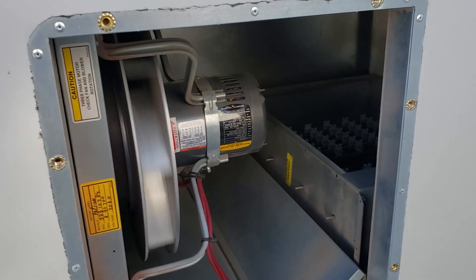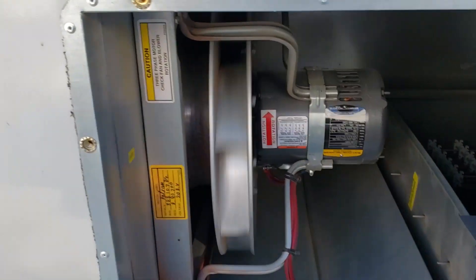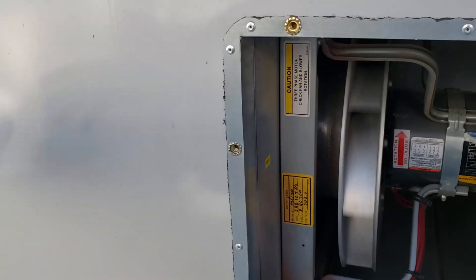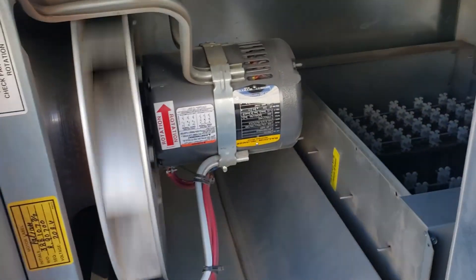In an AAON unit, they use these direct drive, forward-inclined pitched wheels. Basically, it just draws air through the middle from the return, through the coil and this fan, and it pressurizes this compartment with static pressure. Then it pushes it down through the supply air through the reheat coils.